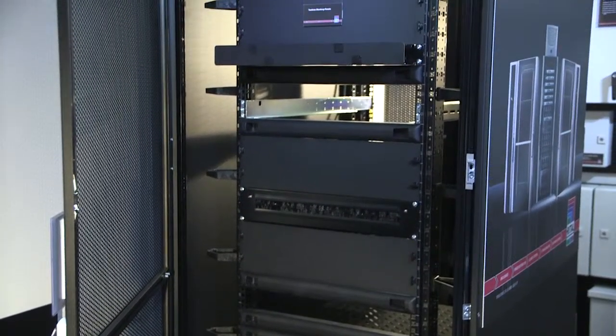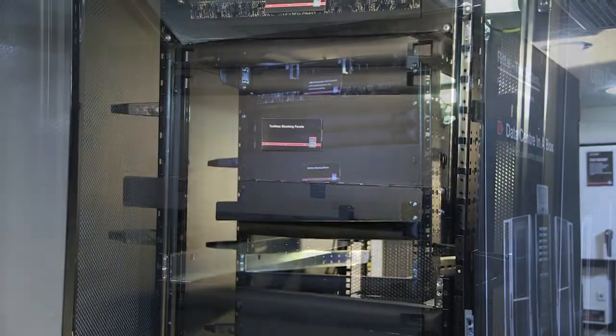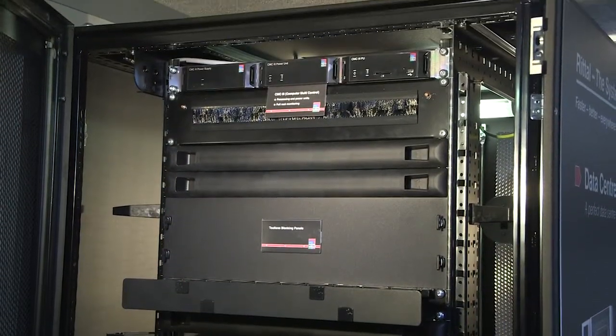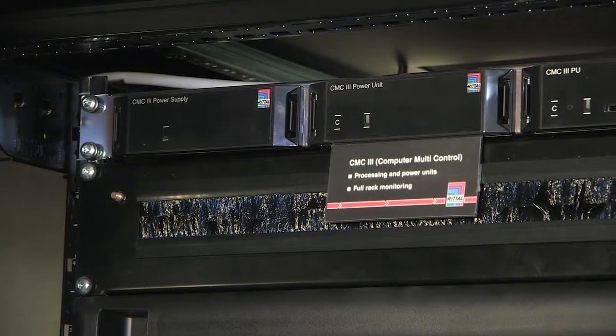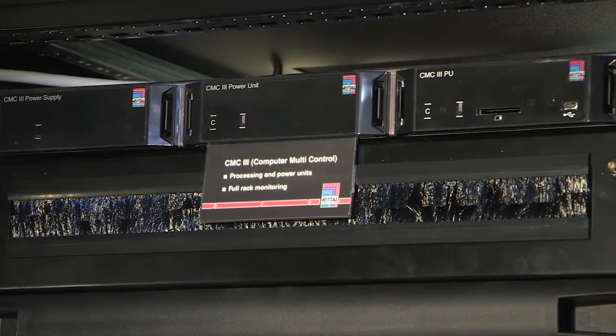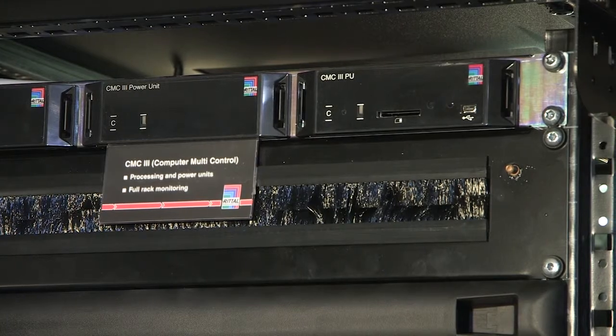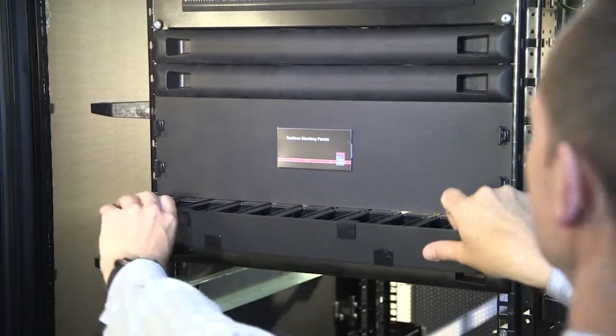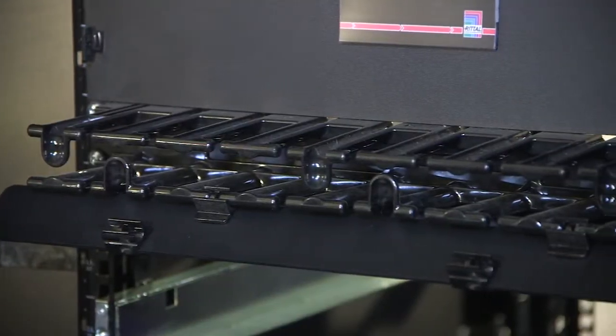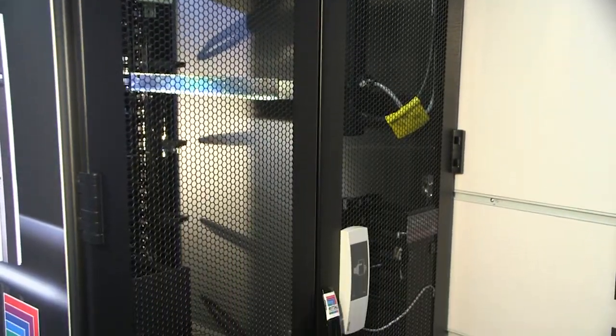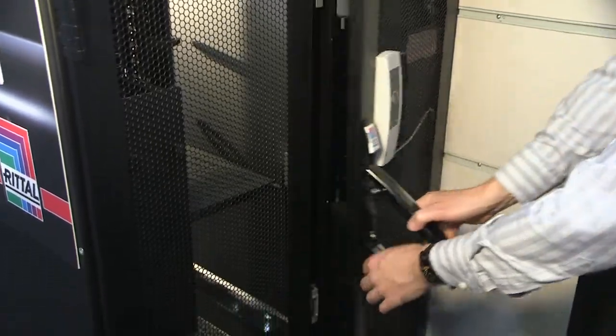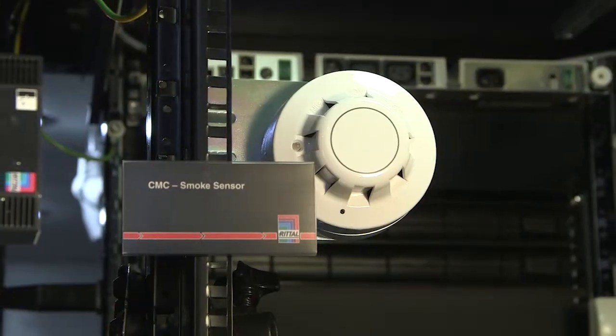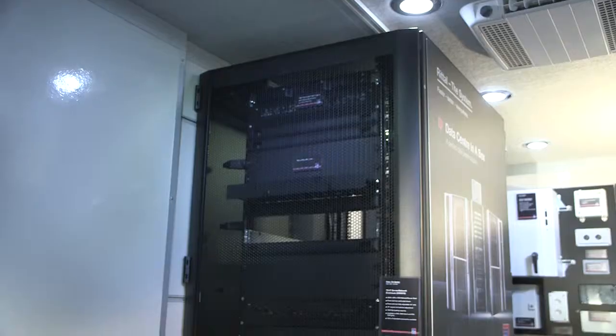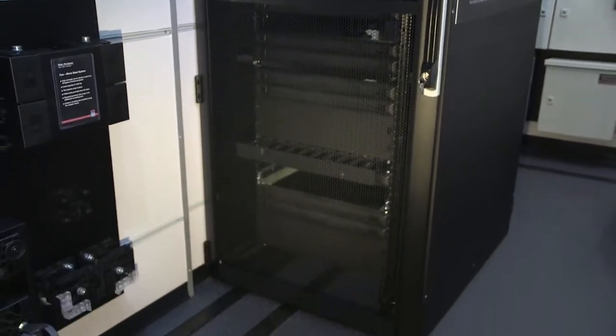The enclosure shown here has been equipped with CMC, or computer multi-control devices. Depending on the rack-mounted sensors chosen, various aspects can be remotely monitored, including heat level, humidity level, vibration, smoke presence, door access, power consumption, and other conditions within the enclosure. A range of devices and functions can be selected, including, as we see here, lighting and cable management panels, all precisely fitted for installation in the standard TSIT enclosure. At the rear of the enclosure, a swipe card module permits authorized access. Inside, we see a power distribution unit, smoke sensor, and other modules. Total static load weight capacity of the TSIT is 1,500 kilograms.